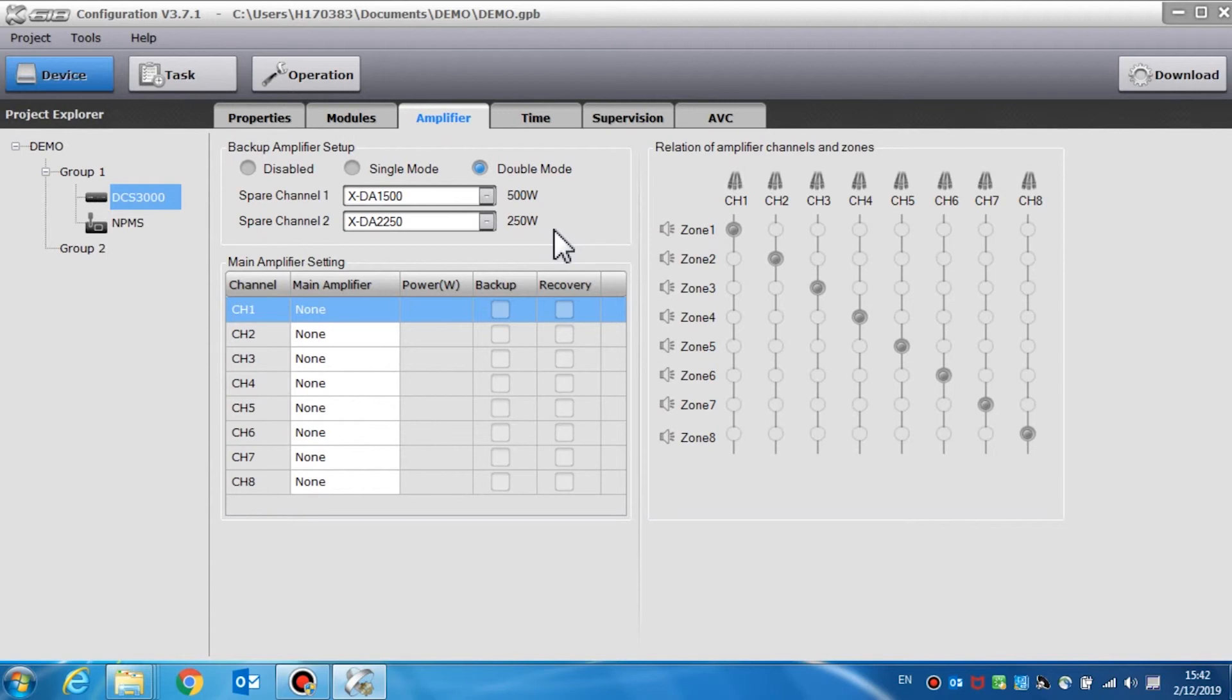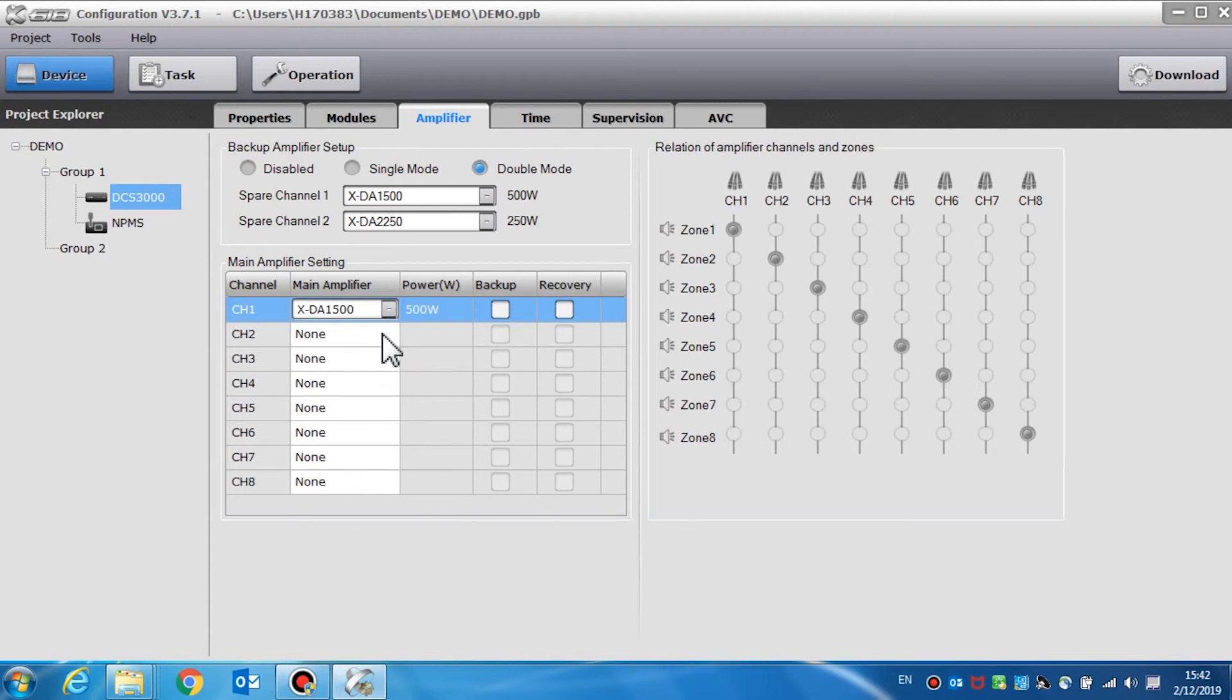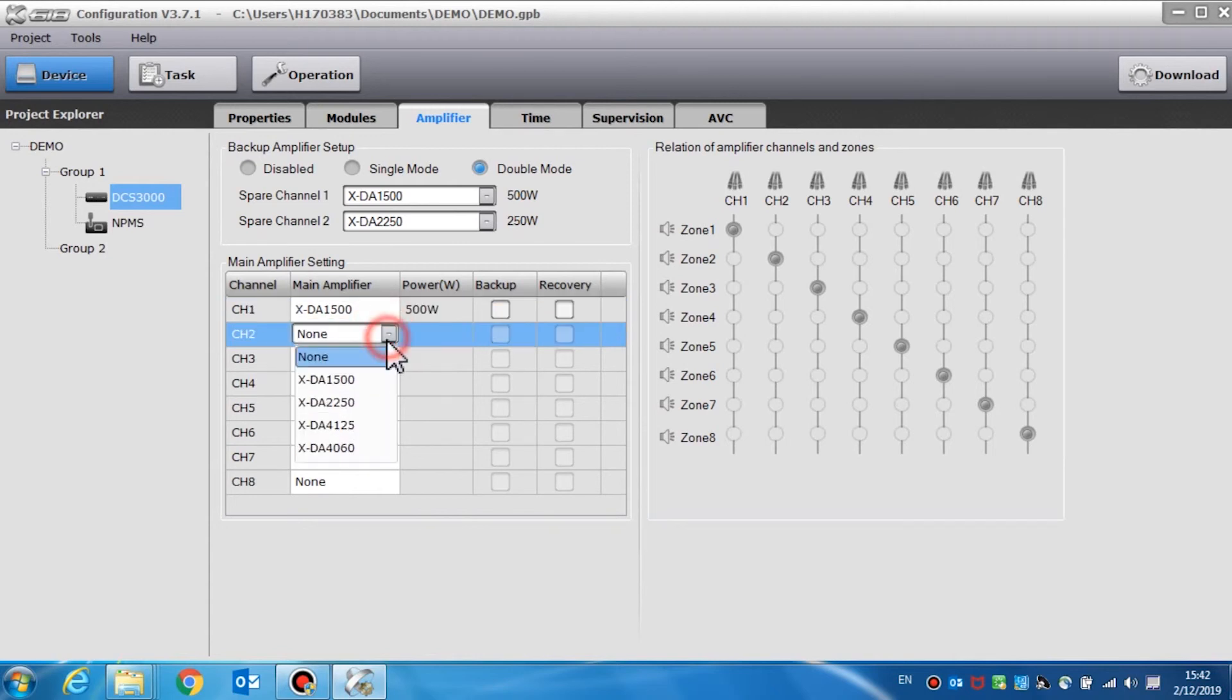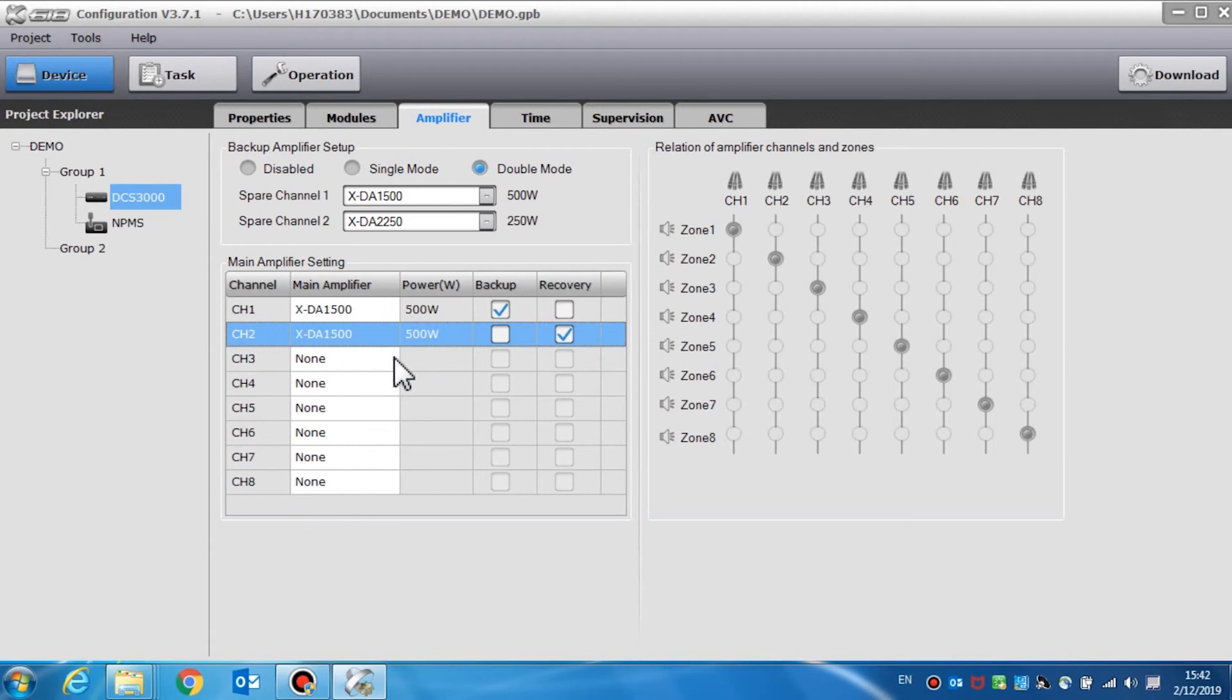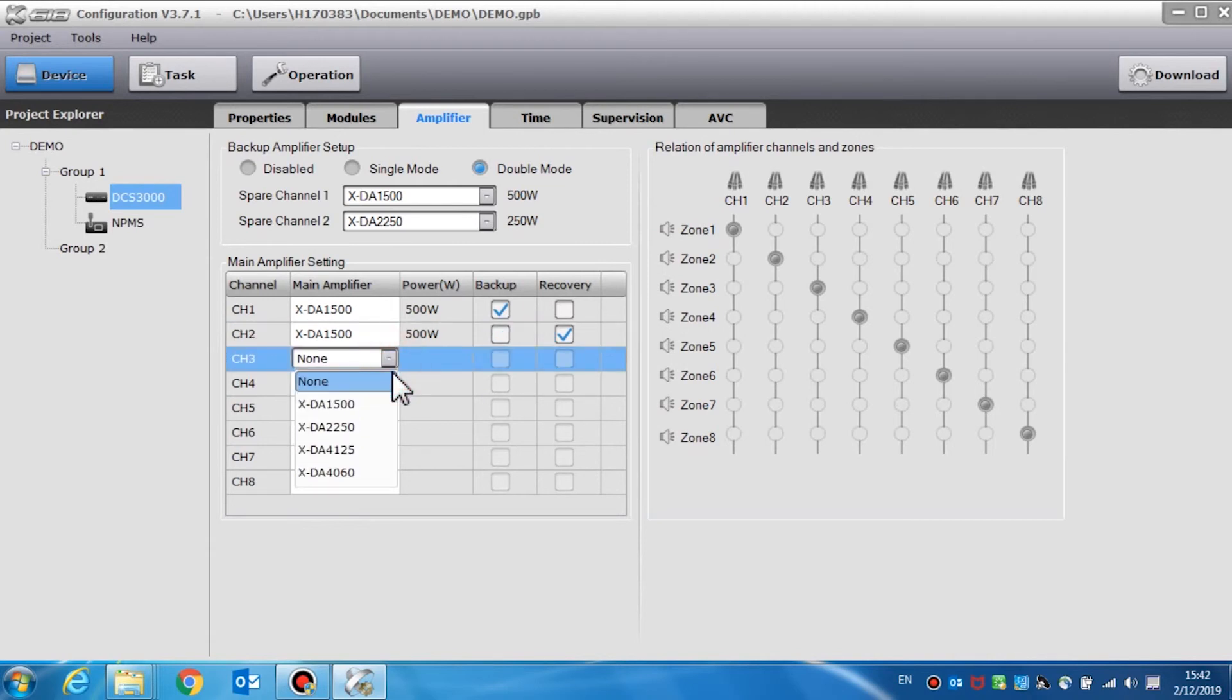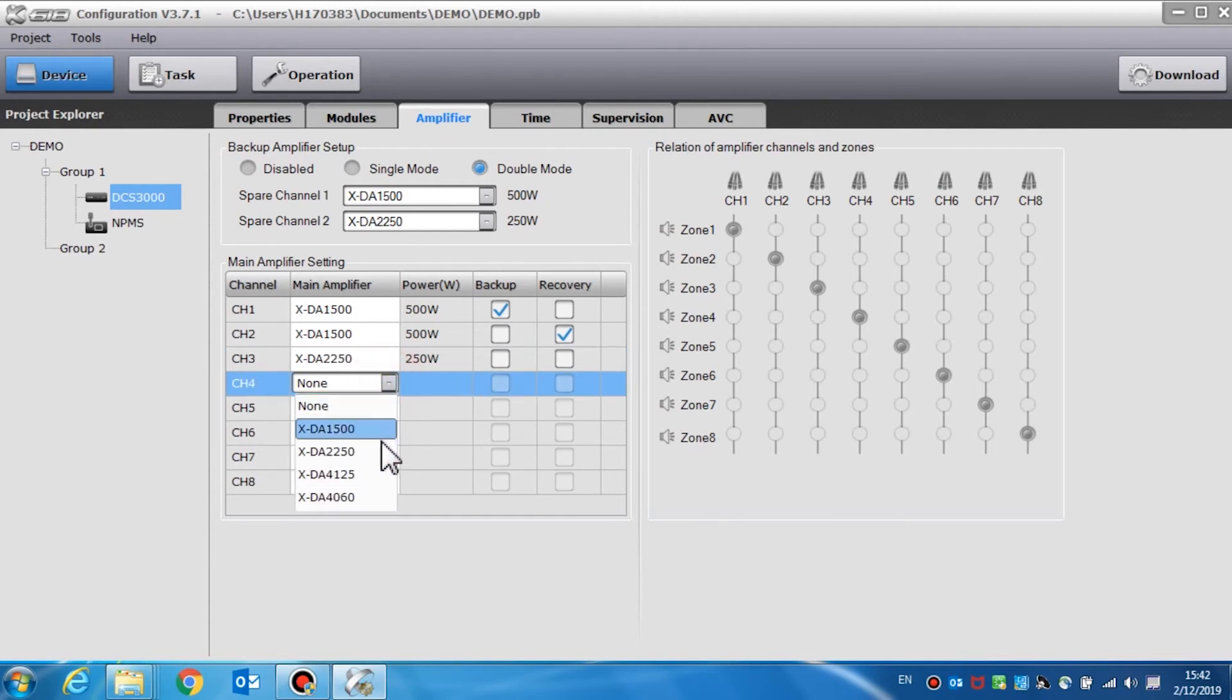The main amplifier setting is to choose the amplifier type for each channel according to how it is set up in the system. We can also set the backup and recovery for the main amplifiers. In the backup, we can select the channel that we want to have backed up. Recovery means the channel could switch between the main amplifier and the backup amplifier. What needs to be emphasized is that that the amplifier supervision should be enabled, otherwise the backup function will not work normally.